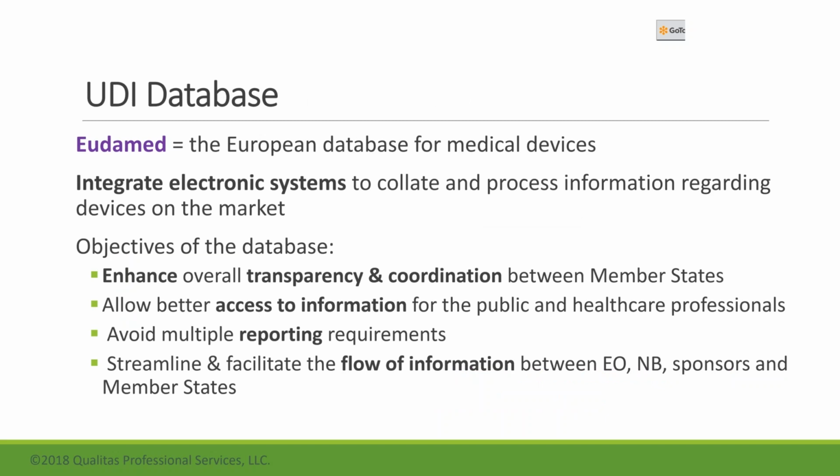And those data elements are going to go into your UDI database. In the FDA, in the US, we have the GUDID, the Global Unique Device Identification Database. In Europe, we'll have the Eudamed. It's the European database for these medical devices. And it's really more than just for UDI purposes. It actually integrates multiple electronic systems to collate and process information regarding medical devices.